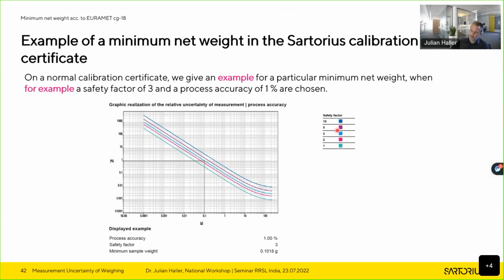So in this example, we say that the process accuracy or maximum allowed relative uncertainty is 1%, and the safety factor that the user wants is 3. Then you have to go to this bright blue line. You just go here, and now you read that you have to weigh in approximately 0.1 gram. And it's also calculated here below in this example. So for any process accuracy required for the processes of the user, so that this can be 0.1%, 1%, 10%, whatever, and an optional safety factor of 1, 2, 3, 4, 5, 10, whatever, the respective weight can be calculated that has to be weighed in to ensure these required process parameters.